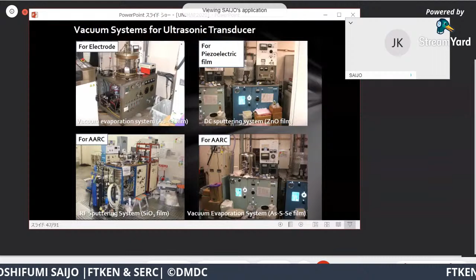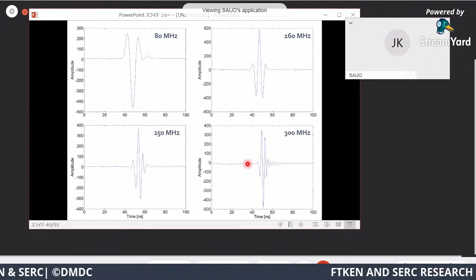So this is the apparatus outline of the ultrasound transducer. And these are the frequency responses: 80 megahertz, 160 megahertz, 250 megahertz, 300 megahertz. You can see the frequency getting higher and the pulse is sharpened. And these are the spectrum analysis. We can observe the 80 megahertz, 160 megahertz. Maybe we made the 250 megahertz, but the pulse response central frequency was about 200 megahertz. And again, this time we made a 350 megahertz ultrasound transducer, but the frequency response is almost 300 megahertz.